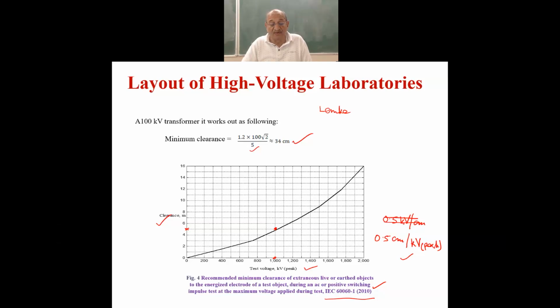In case, at the maximum voltage of the equipment, that voltage is generated by the equipment, and 1.2 is the safety factor applied there, and that works out to be 1.2 into 100 multiplied by root 2 divided by 5, which is about 34. This is a little more stringent calculation. So I would say, with my experience in life, 0.5 centimeter per kVp is a very nice and very good clearance requirement.